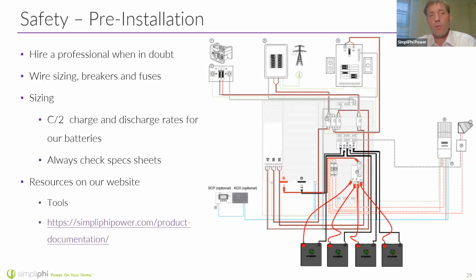All of our batteries have a C/2 charge and discharge rate. That means the capacity divided by 2 hours. So you wouldn't want to charge one of our batteries in 1 hour—you'd want to charge it from 0 to 100% over 2 full hours. That's what C/2 capacity means: you can charge or fully discharge the battery in 2 hours, and we typically specify this as an amperage.